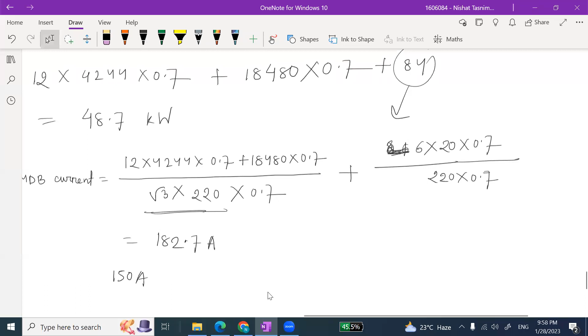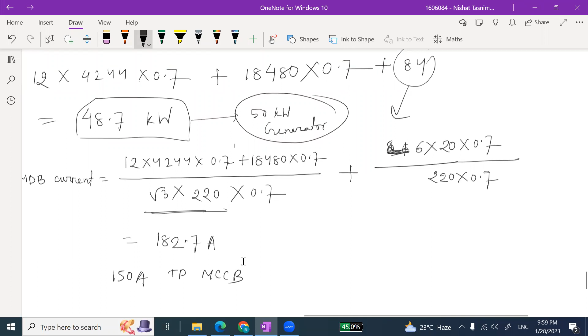And the MDB load was 48.7 kilowatts. So we can use a 50 kilowatt generator, right? So let us write here 50 kilowatt. Okay. We are almost at the end. Only one calculation is left. I'm giving you a 2 minute break.